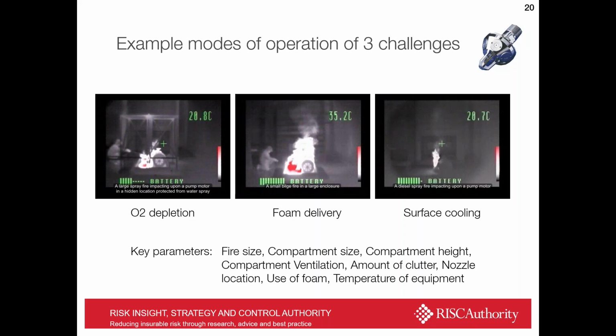Now again, that's not necessarily native to a Watermist system, and small droplets are not actually very good generally at cooling surfaces. But just like the need to deliver foam, this is actually a hybrid system that we produced, which had a combination of small droplets and large droplets. Small droplets to give you all the benefits of intense atmospheric cooling and fantastic steam production, as a standard Watermist system might have, but it also provided large droplets, which were very good for surface cooling and also the delivery of foam to the fire. I'm sorry I couldn't bring you those videos.